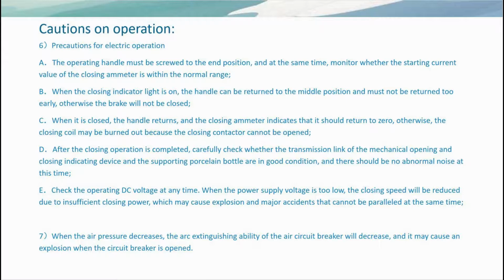A. The operating handle must be screwed to the end position, and at the same time, monitor whether the starting current value of the closing ammeter is within the normal range. B. When the closing indicator light is on, the handle can be returned to the middle position, and must not be returned too early, otherwise the brake will not be closed. C. When it is closed, the handle returns, and the closing ammeter indicates that it should return to 0, otherwise, the closing coil may be burned out, because the closing contactor cannot be opened.